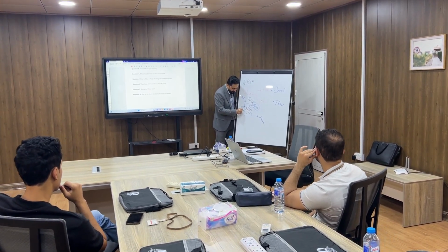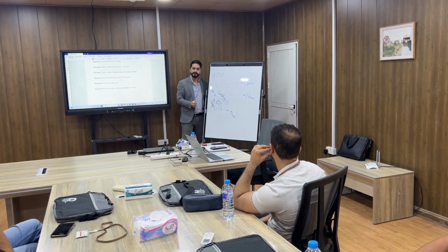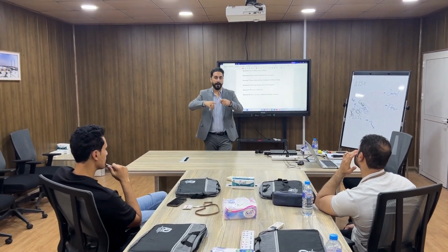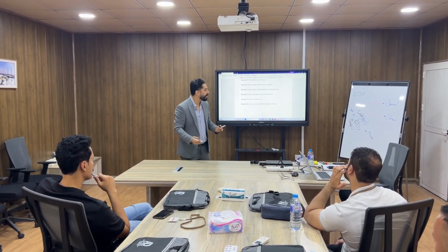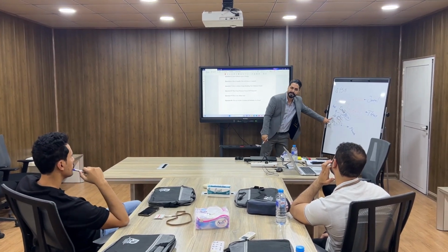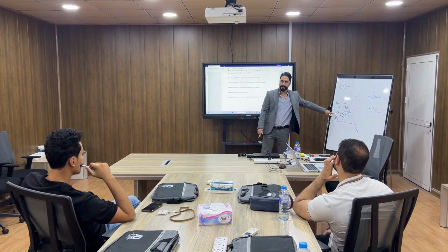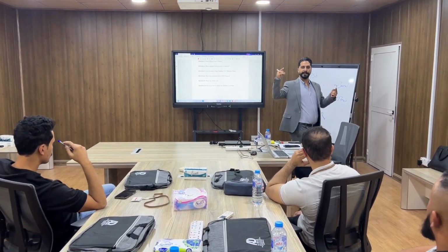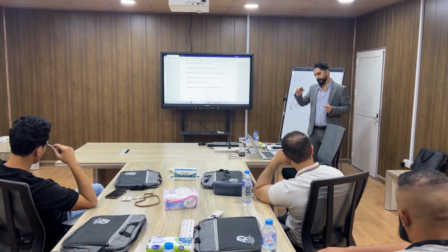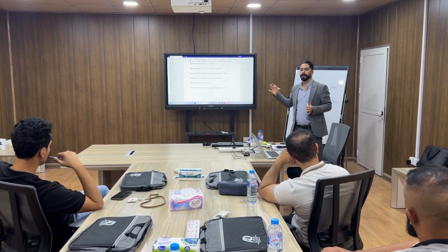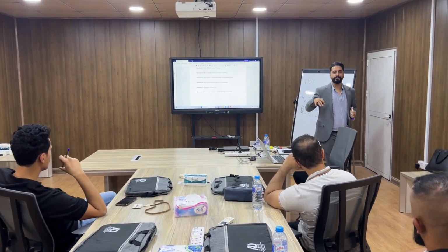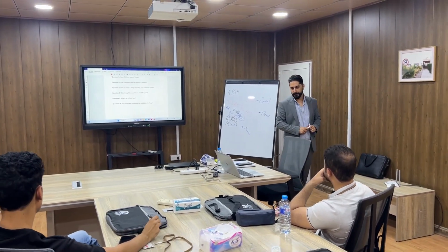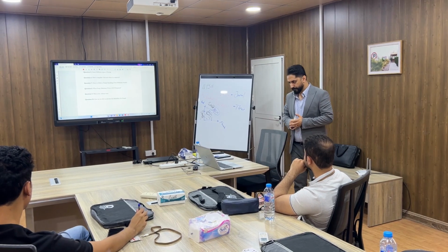the flow rate is not stable. Of course. That's why you need to do some modification on the impeller, to be able to work in unstable sections of the pump. And we are going to talk about it too. It's called impeller trim. By reducing the diameter of the impeller according to the standard, which is API 610, you are going to use the same pump for different sections in the operation.